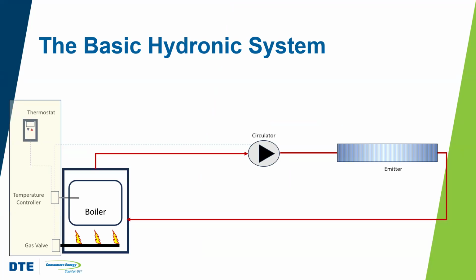There's a temperature controller for the boiler itself, for the water in the boiler, right? And this modulates the burners to make sure that the water temperature in the boiler stays between its set point and its preset differential. Usually it's about 10 degrees. So if the boiler set point is 160, at 150 the burners would come on. If the water temperature in the boiler is between 150 and 160, the burners would be cycled off, right? So we want to keep the boiler on so that it's ready to go whenever there is a call for heat, but we can cycle those burners on and off so that we don't overheat that water, right? This would also control the pump and turn it on as well, right?